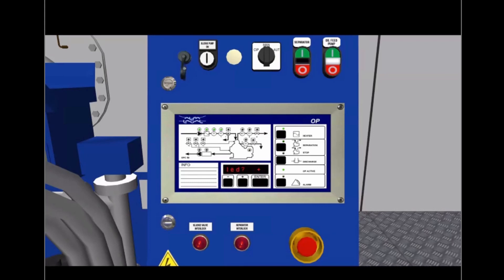If, however, the bowl has been dismantled, press the plus button. If the bowl has been dismantled and then reassembled according to the instructions in the service manual, press the plus button again. If the bowl has been cleaned, press the plus button. An automatic calibration of the system is then carried out.